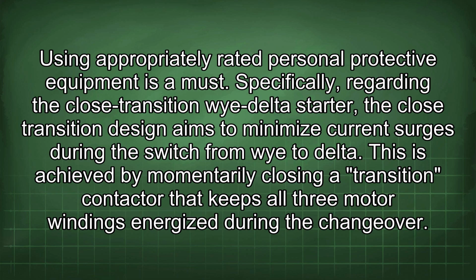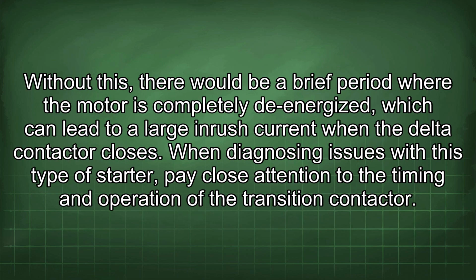This is achieved by momentarily closing a transition contactor that keeps all three motor windings energized during the changeover. Without this, there would be a brief period where the motor is completely de-energized, which can lead to a large inrush current when the Delta contactor closes. When diagnosing issues with this type of starter, pay close attention to the timing and operation of the transition contactor.